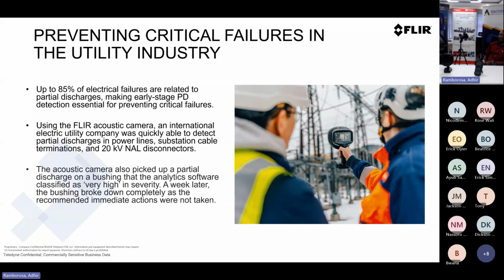So the acoustic image also picked up a partial discharge on a bushing that the analytics software classified as very high severity. A week later, the bushing broke down completely, as predicted. So that means this unit can classify the severity of that partial discharge. That is actually correct. That is very correct. So it's using AI technology to classify based on the PRPD pattern. But I think you're going to take us into more detail with that.